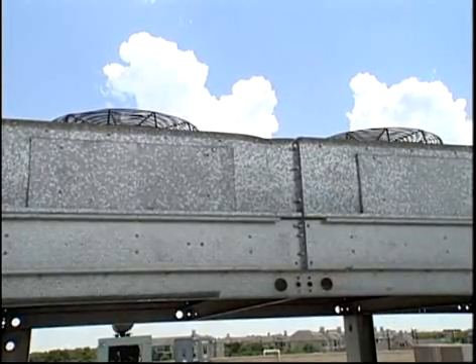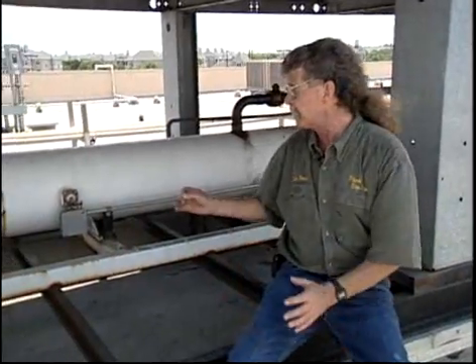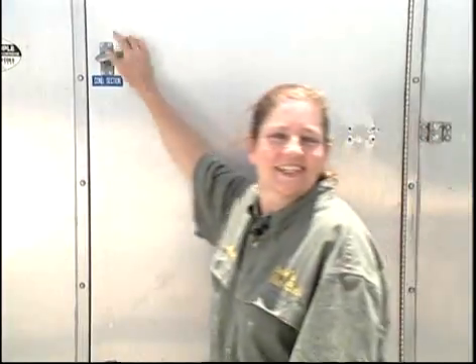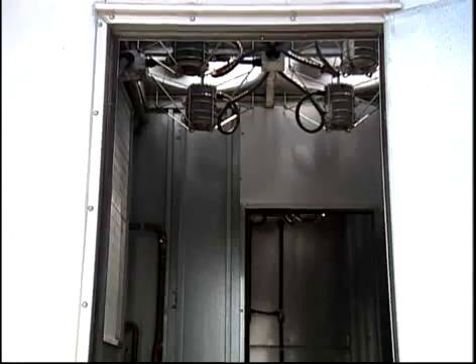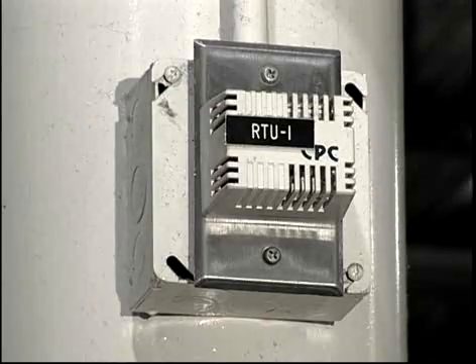As you can imagine, all of these evaporators require a lot of refrigerant. This is one of the larger liquid refrigerant receivers used in the commercial refrigeration industry. It must maintain a level of refrigerant sufficient to supply all of these evaporators, and at the same time have enough room to pump the system down in case of maintenance or repairs. Indoor ambient temperatures and humidity must be strictly controlled, or the evaporators downstairs won't cool properly. The temperature and humidity sensors are located inside the store near the doors and constantly send information back to the main controller.